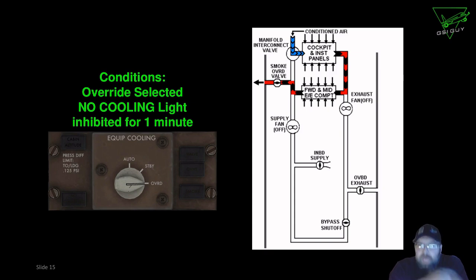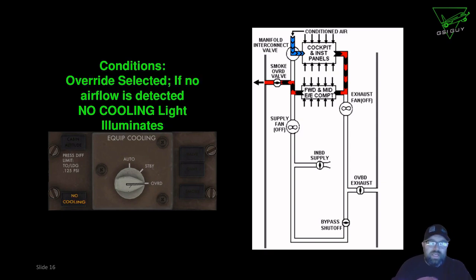The smoke light will extinguish when the smoke is no longer there. The no cooling light will again be inhibited for a minute because we need to get that airflow, right? We need to sense that airflow coming across that sensor. After that minute, if for some reason the valve didn't open or there's no airflow there, and the no cooling light comes on, now you've got all kinds of issues that you still have to fix, because now you've got a problem where you had smoke. You can't go back to the auto position. You can't cool the airplane or the equipment by going into the override position because the valve won't move. So again, you're stuck at 90 minutes losing things, landing at the nearest suitable.